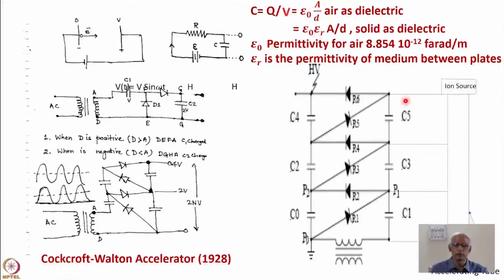Here there is a capacitor of capacitance C. Calculating capacitance is important: for two parallel plates it is epsilon naught A over D, where A is the area of the plates, D is the distance between them, and epsilon naught is the permittivity of air. If a different medium is used, this gets multiplied by epsilon r, the relative permittivity of that medium. For example, enclosing the system in SF6, which has a higher dielectric constant, lets you reach higher voltages.